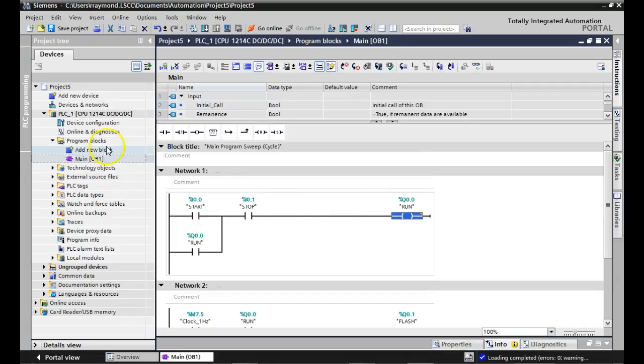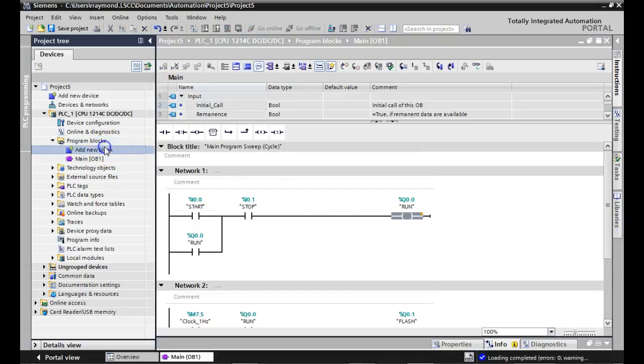So what happened, y'all listen up. What was happening in the CC is that yesterday we built a function block, right? We built the subroutine. And we were supposed to delete it, right? But CC still had that function block over here, but the new program didn't contain a what? Function block. So if we looked at the error message, it said inconsistent configuration.